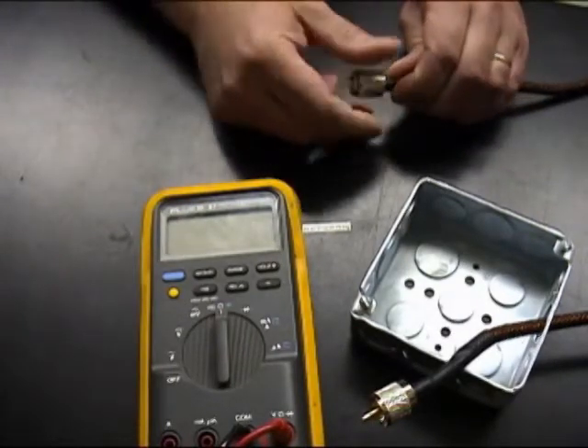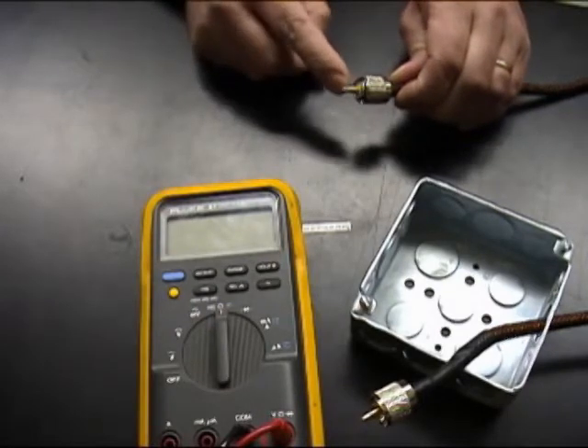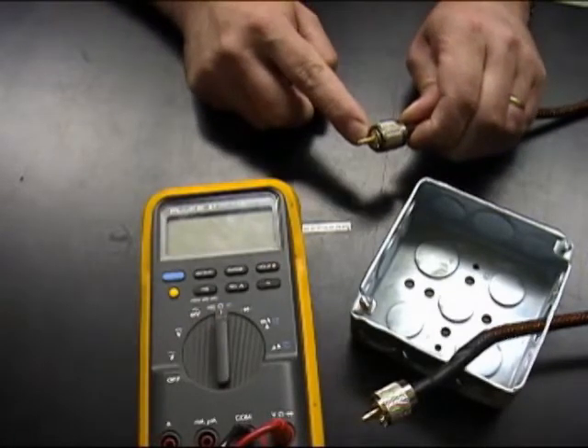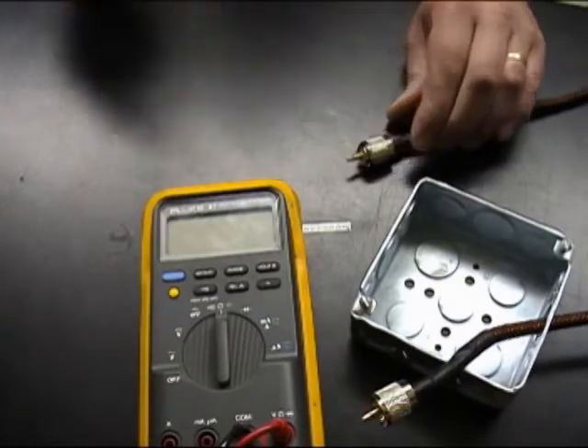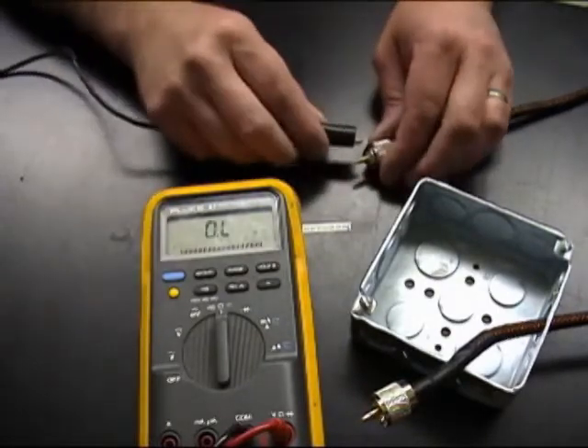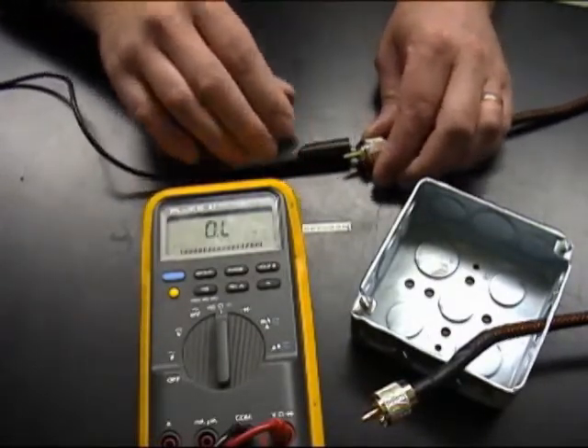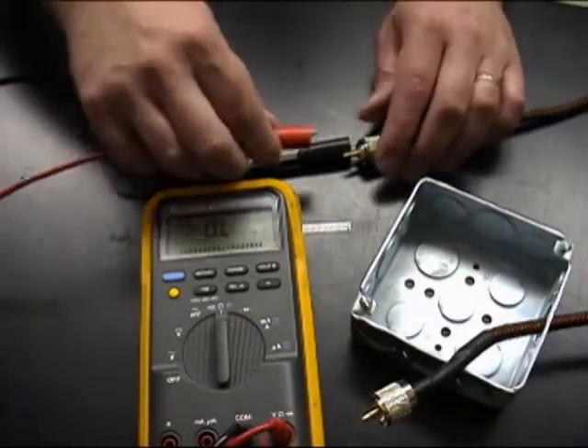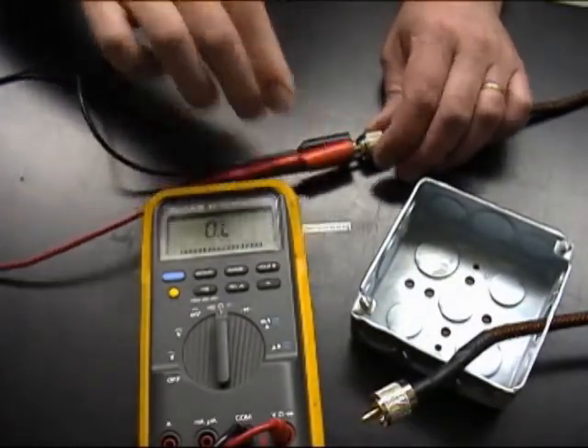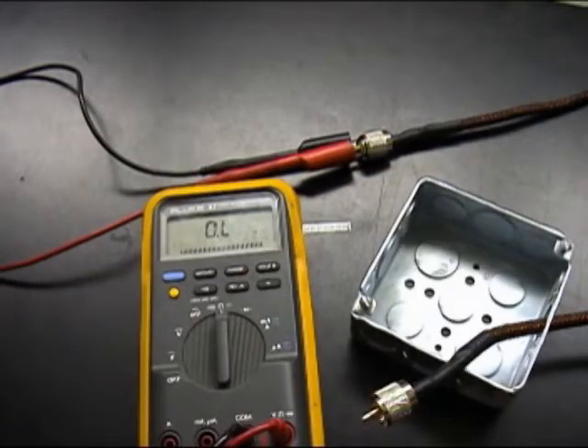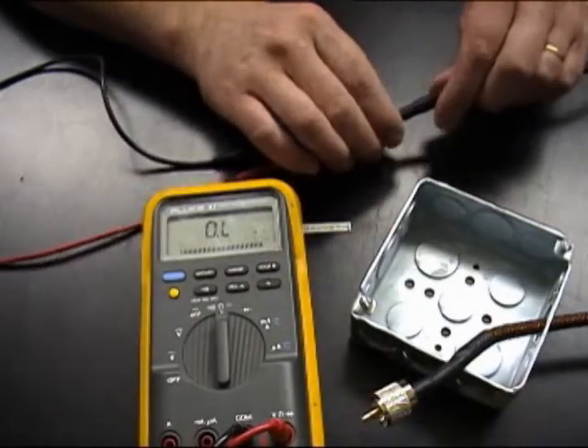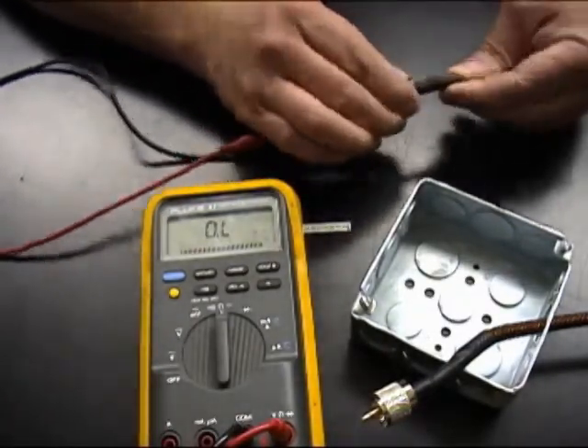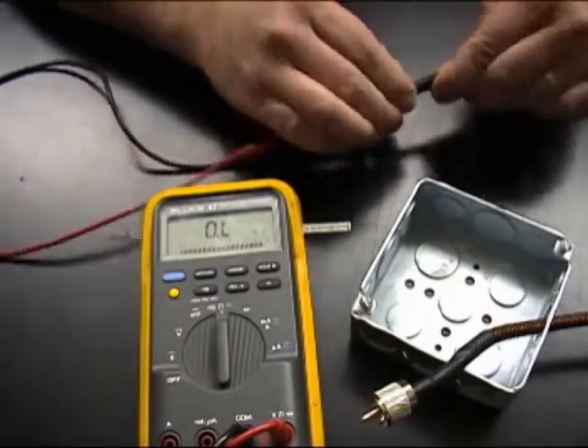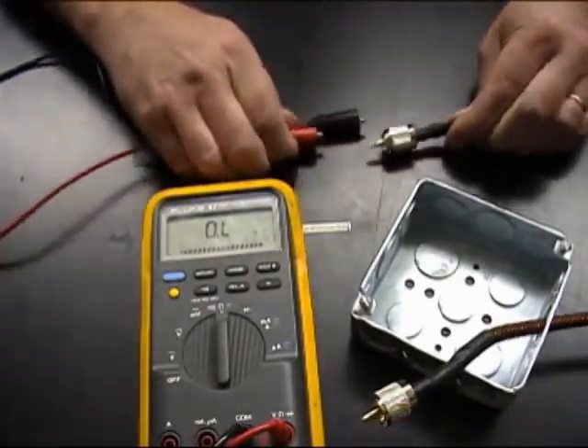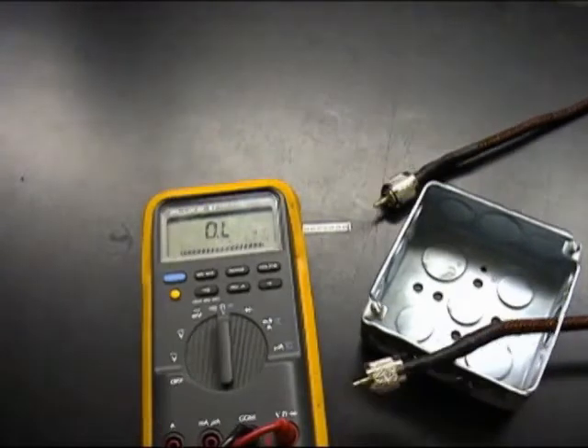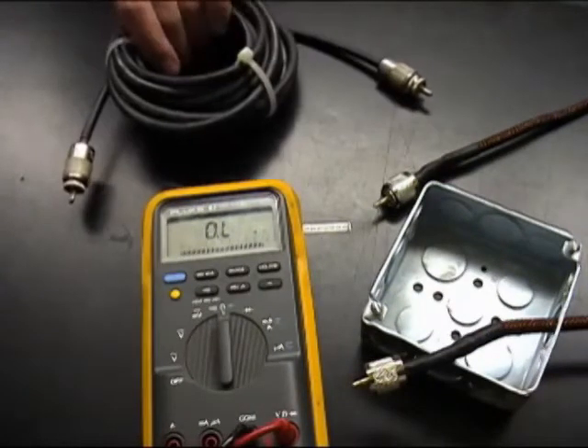With the next step, we will thread back the coupling ring enough so that we can hook up one of the multimeter probe leads to the plug body. Then, take the other multimeter probe lead and connect it to the pin of the plug body. With the probe leads hooked up, the multimeter must continue to read an open circuit. Next, flex the connector. During the flexing process, the open circuit reading must remain stable. If it does, you pass the insulation test.